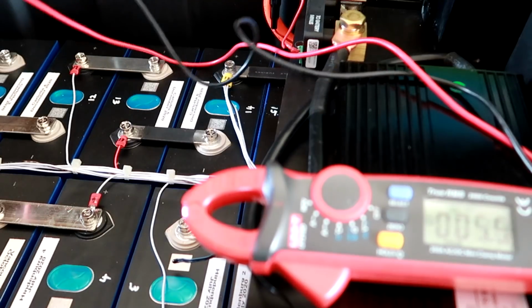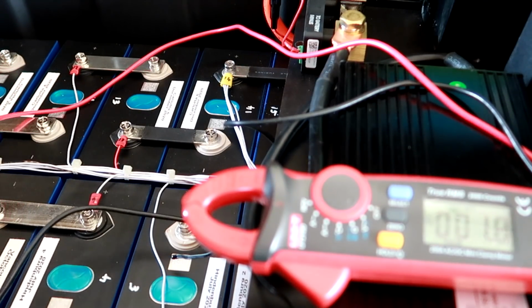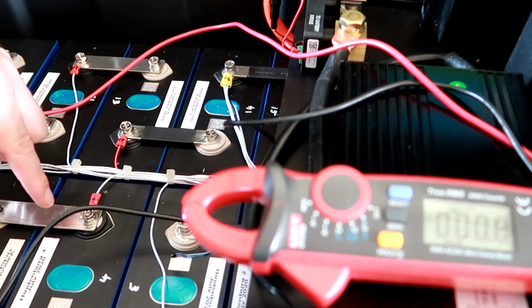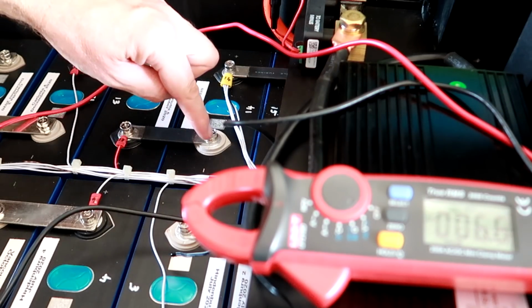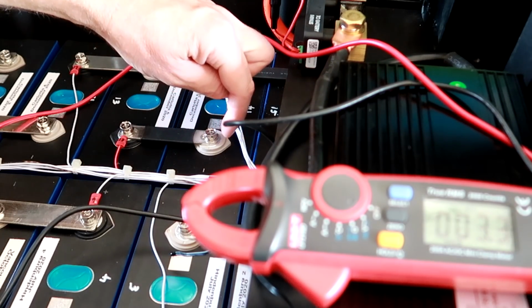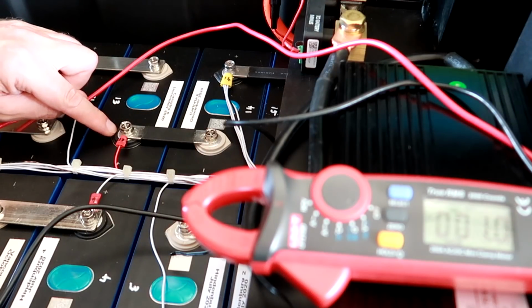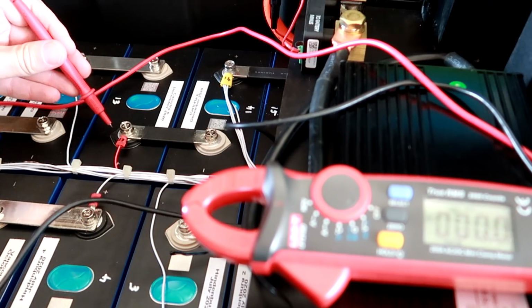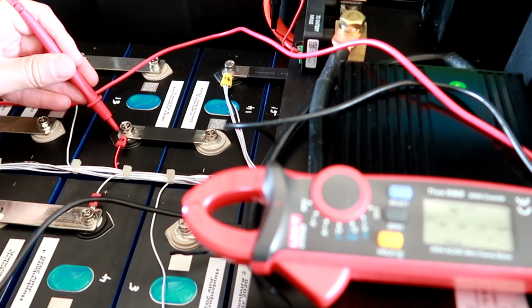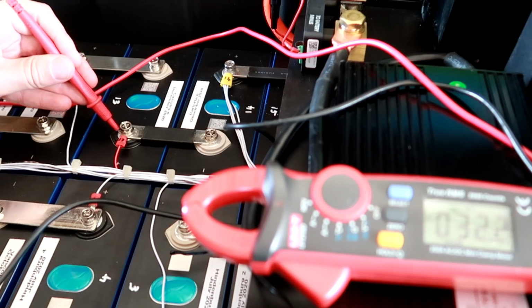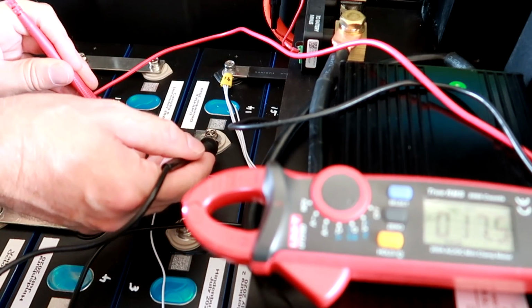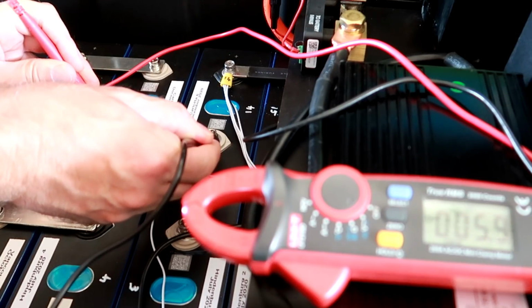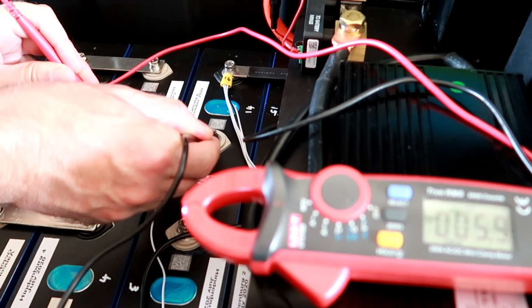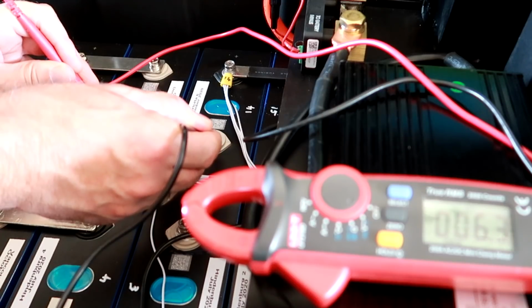Okay, so what I will do now is measure the voltage drop across the bus bars, directly from the terminal of the battery to the other terminal. It's peeking out a little bit from the side, so I can put my probe here on the terminal and on the other side as well. 5.66 millivolt voltage drop.